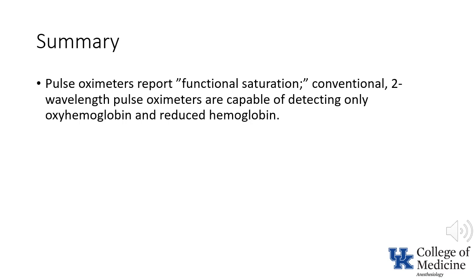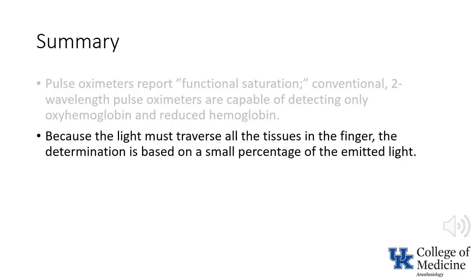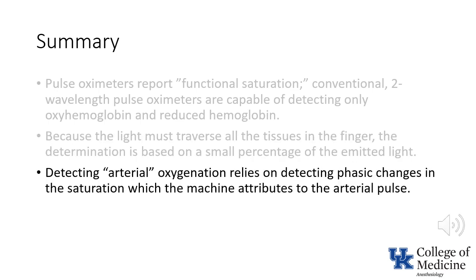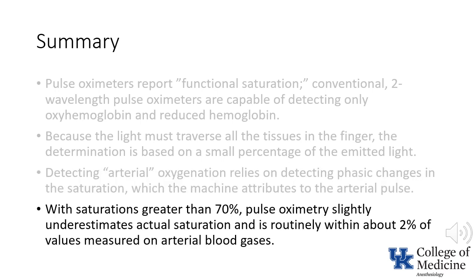In summary, pulse oximeters report functional saturation. Conventional two-wavelength pulse oximeters are capable of detecting only oxygenated hemoglobin and reduced hemoglobin. Because the light must traverse all the tissues in the finger, the determination is based on a small percentage of the emitted light. Detecting arterial oxygenation relies on detecting phasic changes in the saturation, which the machine attributes to the arterial pulse. With saturations greater than 70%, pulse oximetry tends to slightly underestimate the actual saturation, but is routinely within about 2% of values measured on arterial blood gases.